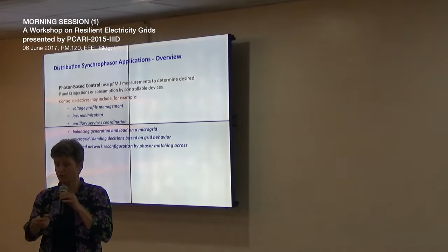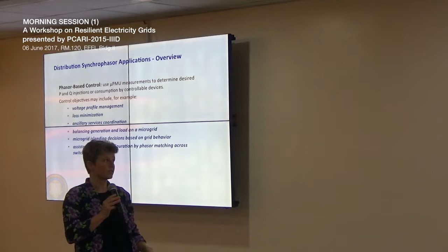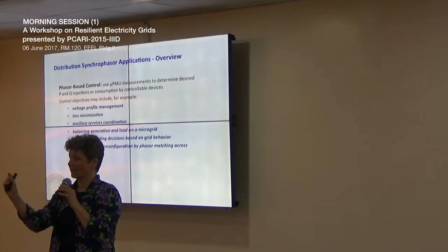You could use control for any number of applications there, including for microgrids and for reconfiguring networks, because often, for instance, if you want to close a switch between two parts of the network, you don't want to close that switch if there's a big voltage difference between them. So phasor-based control would allow you, in theory, to actually get that phasor difference to zero before you close the switch, making it very smooth and seamless.